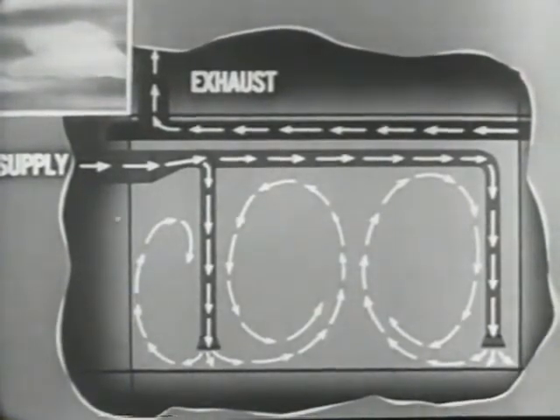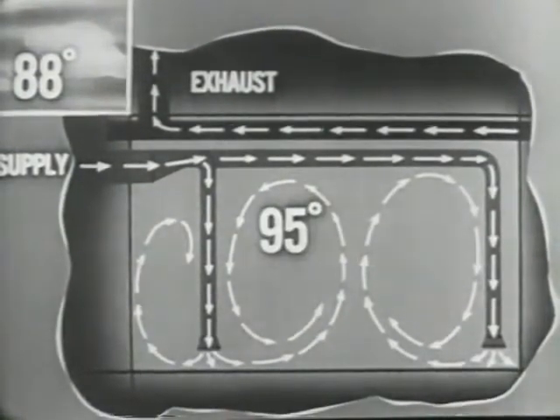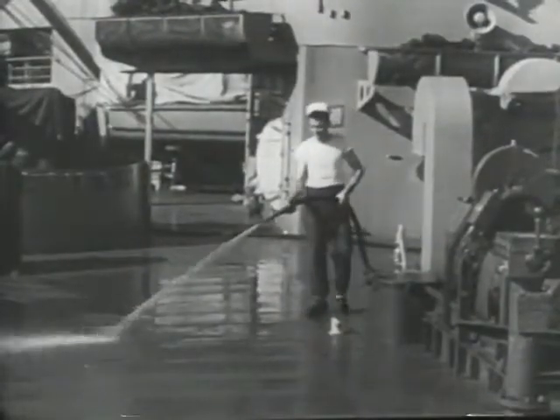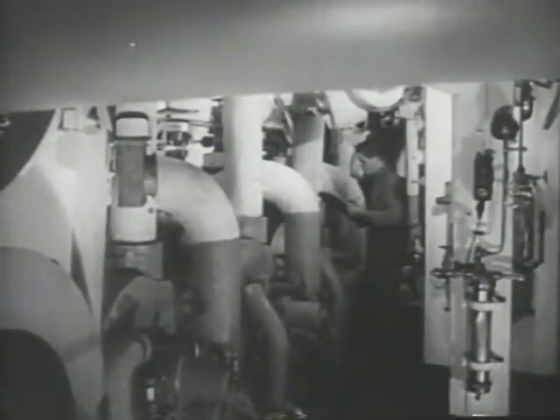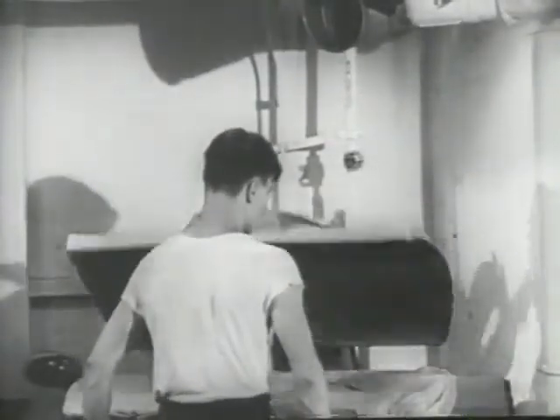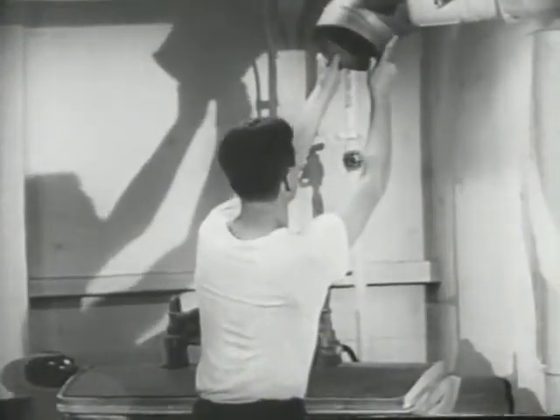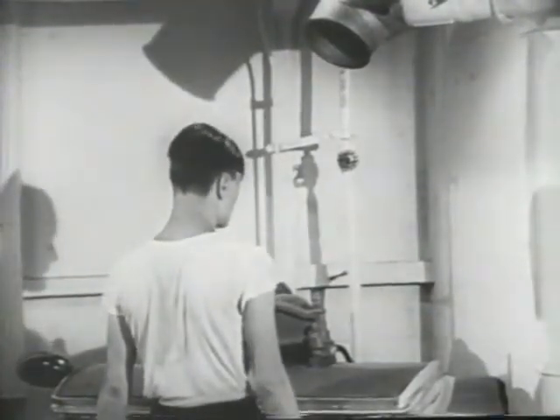If the temperature of the outside air is 88 degrees, the temperature in the berthing spaces should be no more than 95 degrees. Obviously, in extremely hot areas, ventilation air alone is inadequate. The installation of additional bracket fans will help, as well as frequent wetting of decks exposed to the sun. In very hot spaces, such as engine rooms, laundries, galleys, and pantries, it is not practical to maintain satisfactory temperatures throughout. So a high-velocity blast of outside air is directed toward operating stations, creating an area of cooler, turbulent air into which personnel can step for relief.